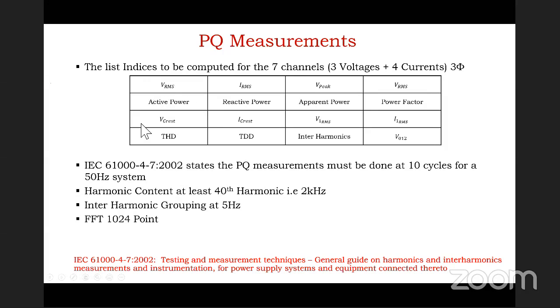You need to calculate RMS voltage, active power, crest factor, total harmonic distortion, and you have to do that for peak value, RMS value, many things. So all these need to be calculated, and you have to find out up to the 40th harmonic, meaning minimum 2 kilohertz is the frequency that needs to be handled, and you have to take at least a 1024 point FFT, so 1024 points have to be saved to perform the entire FFT.